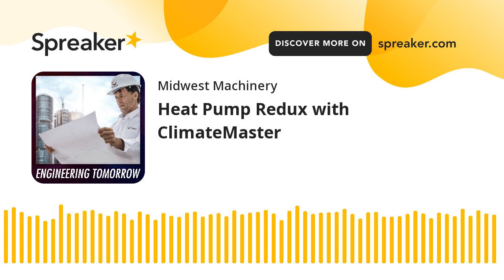The other component is a loop pump. Now, the loop pump is a critical operation to the system. The pumps are installed downstream from the tower and the boiler and upstream from the heat pumps to ensure positive water pressure throughout the entire system. The system pumps can either be constant or variable flow pumps, and there's other options for pumps as well.